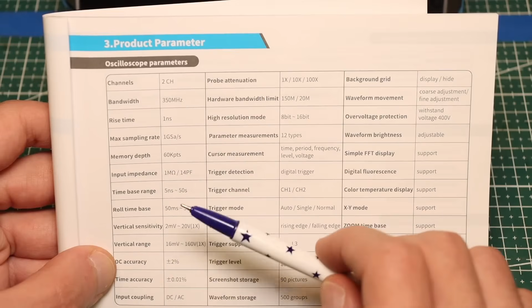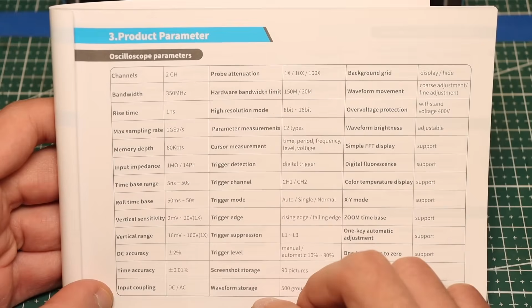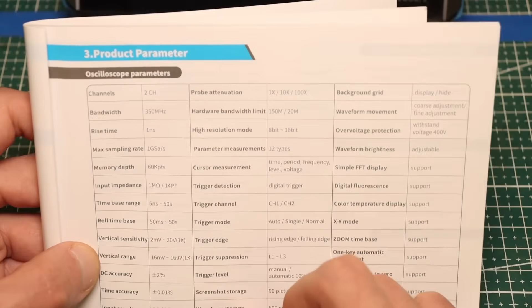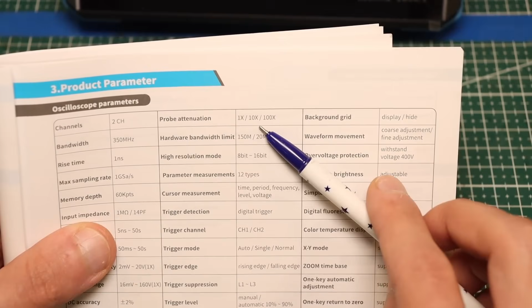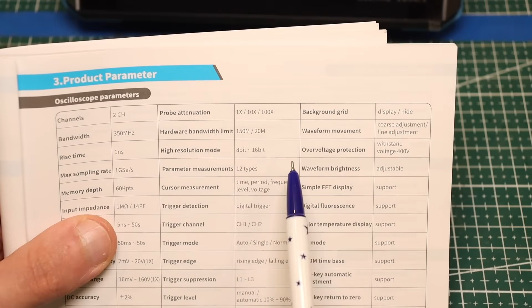It's enough to study even very small voltage ripples. For example, if you need to examine highly stable power supplies, this is actually pretty good, as it provides the necessary accuracy and stability for such tasks. So that's about the measurement accuracy, the input, and the probe, which are all important aspects to consider when assessing your equipment. Well, I don't think there's any need to explain further. If you set a certain divider on the probe, you also need to set the corresponding value in the oscilloscope software so that it calculates the vertical scale parameters correctly.